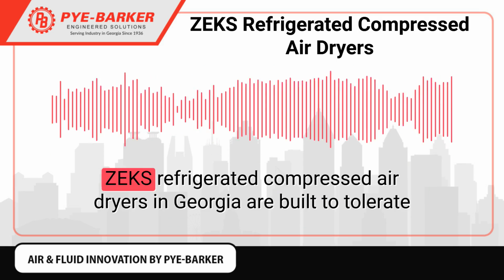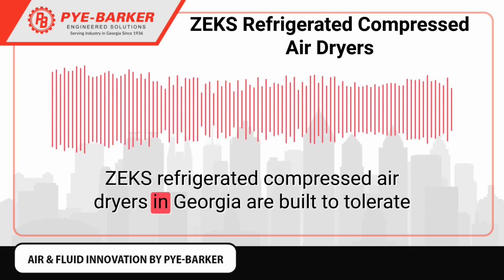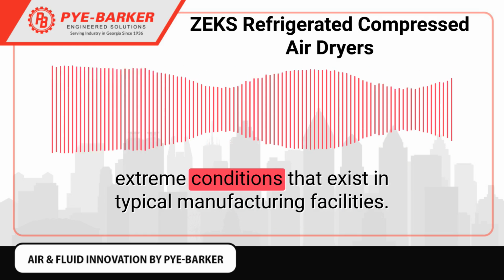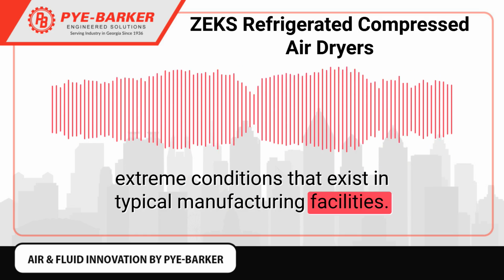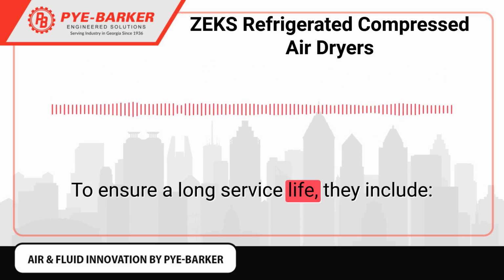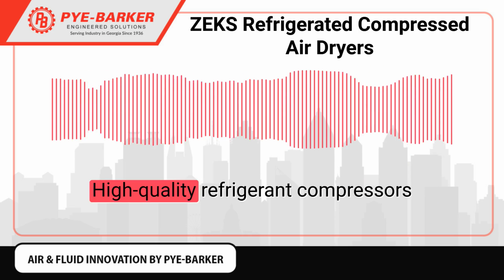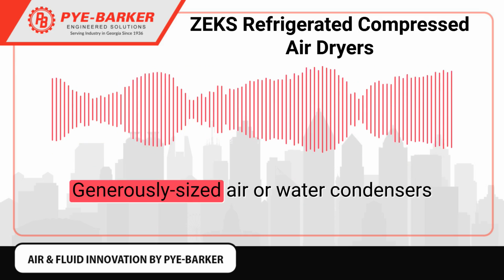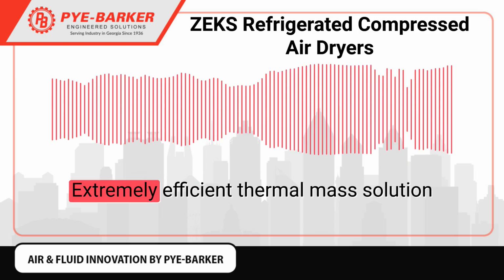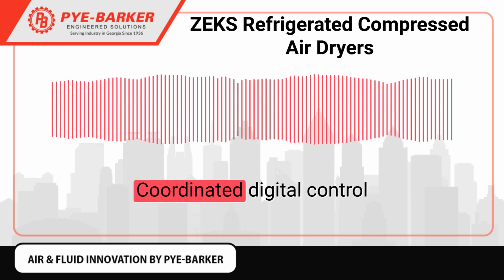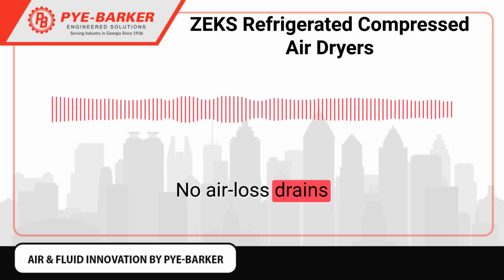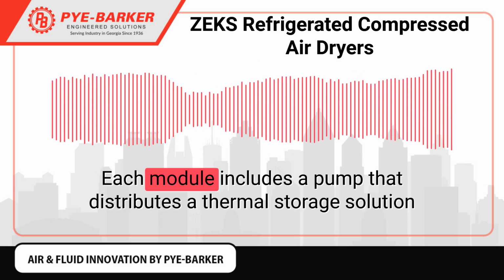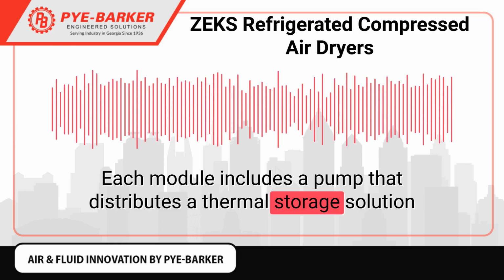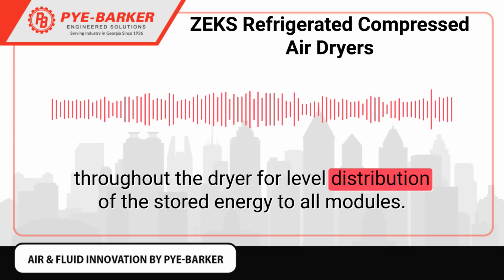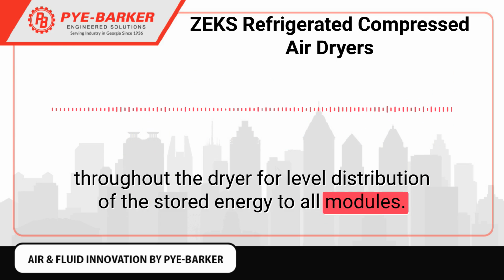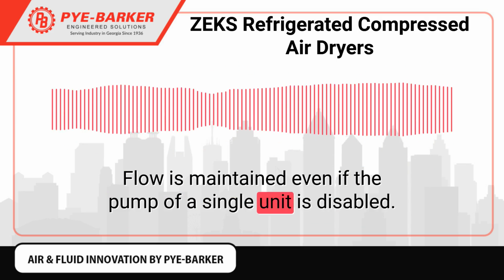Dependable operation. ZEKS Refrigerated Compressed Air Dryers in Georgia are built to tolerate extreme conditions that exist in typical manufacturing facilities. To ensure a long service life, they include high-quality refrigerant compressors, generously sized air or water condensers, extremely efficient thermal mass solution, coordinated digital control, no air loss drains, and consistent pressure dew point. Each module includes a pump that distributes a thermal storage solution throughout the dryer for level distribution of the stored energy to all modules. Flow is maintained even if the pump of a single unit is disabled.